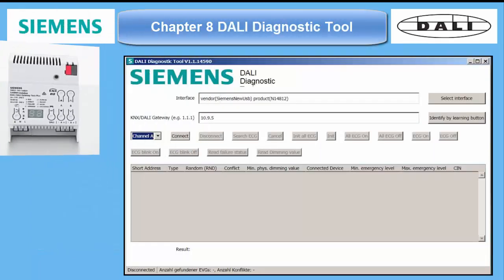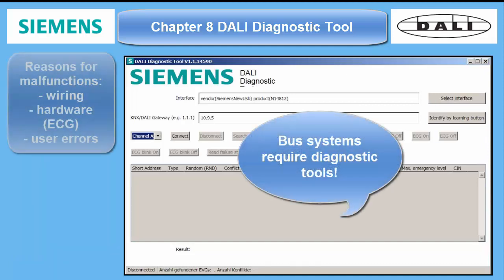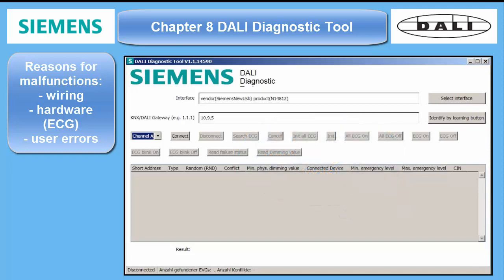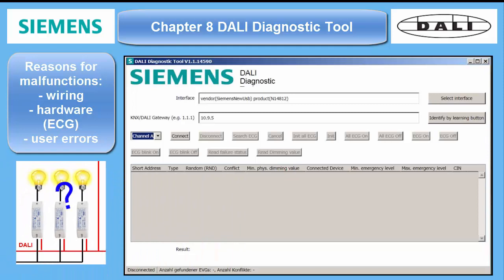The operation of any bus system often causes trouble, which can't be solved simply by trying to download the bus devices once and once again. The reason for the malfunction can be the bus wiring itself or defective hardware. Sometimes also user errors are responsible for certain malfunctions. For DALI, in most cases from our experience, the ECGs are causing the trouble, not the gateways.